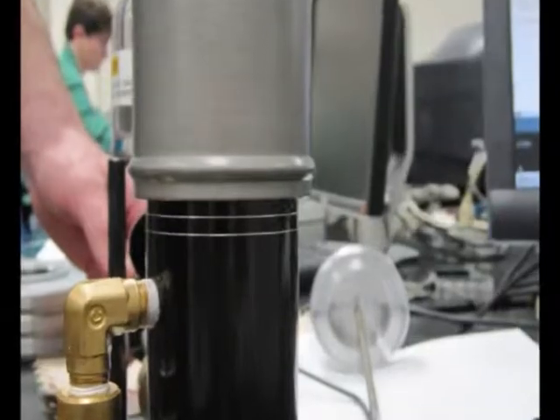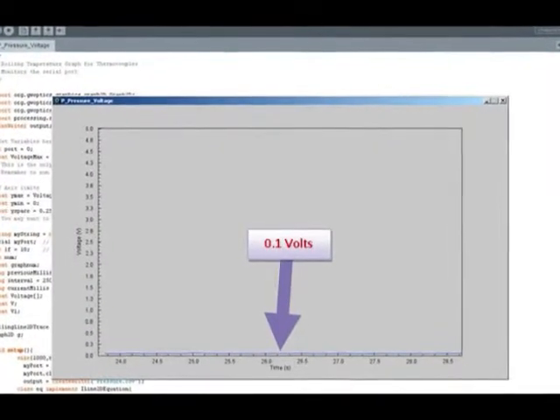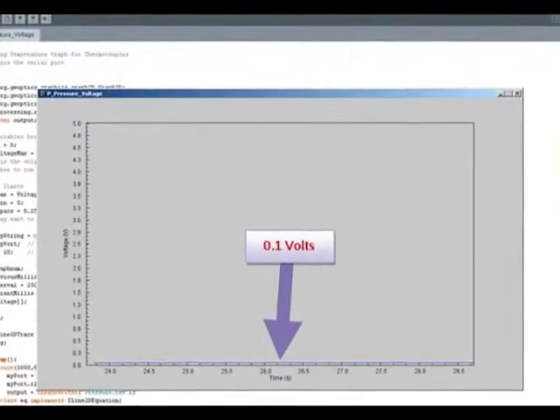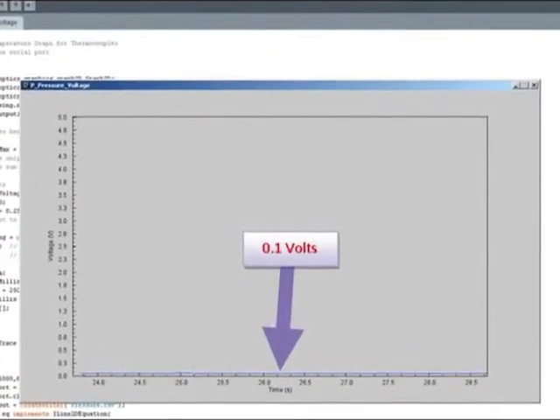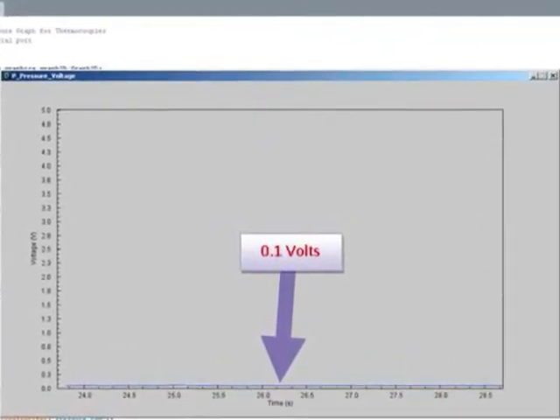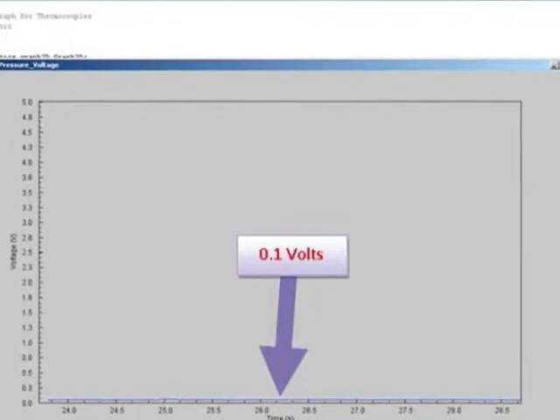Slowly turn the pump screw clockwise until the piston floats. The ideal float position is between the middle 2 horizontal reference marks. With the piston floating, there is a pressure of 5 psi in the transducer. Use processing to record the output voltage again, then rename and save the file to your desktop.